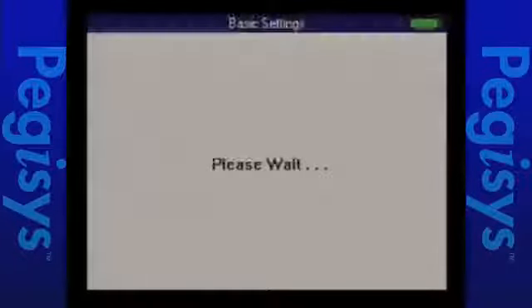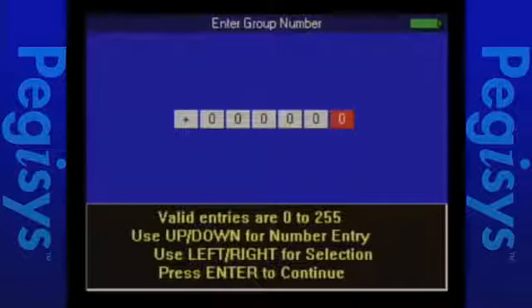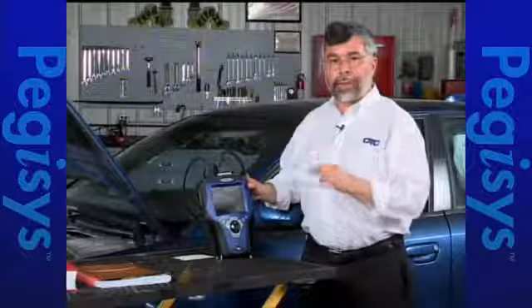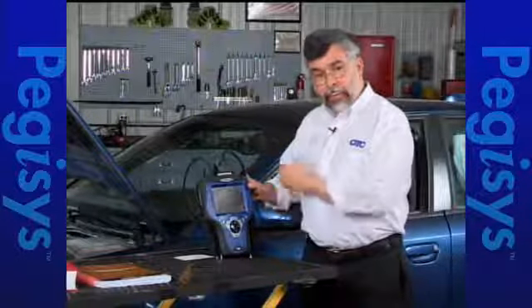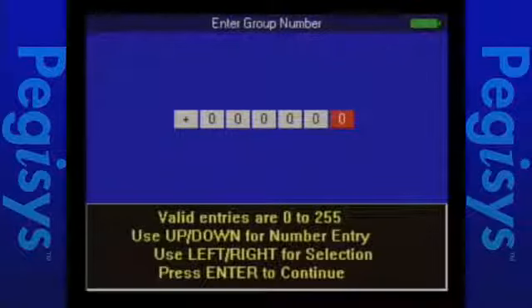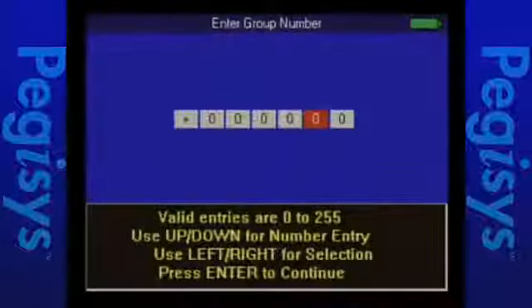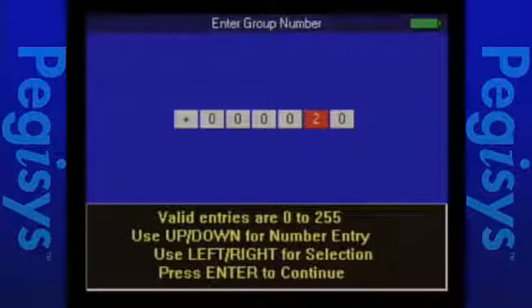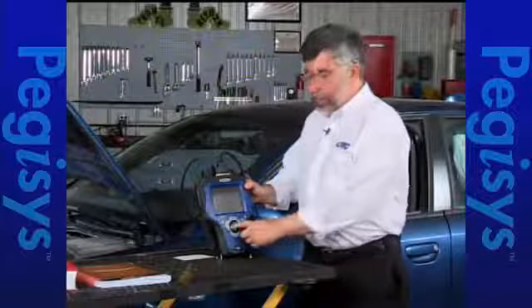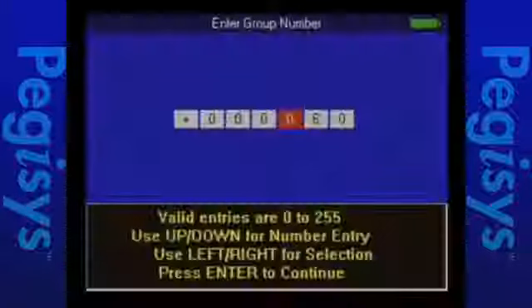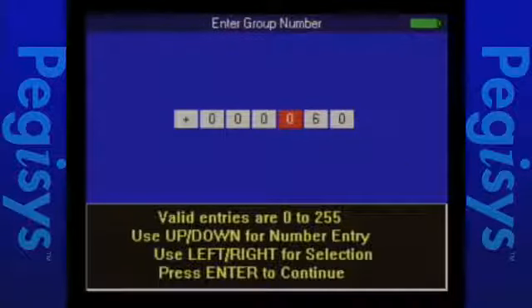When you do, up will come my group number block, and we're going to change our values. Remember, the number I'm looking for is 060. So I've got the furthest one to the right, the 0, highlighted in red. You would change that number if you had to by scrolling up or down. So I'm going to bring it back to 0. I'm going to scroll over to the next digit. You'll notice the second one's now highlighted in red, the second one from the right. I'm going to scroll up till I get to 6. If I had to change my 3rd digit, which I don't because it's already at 0, I would scroll to the left once more, highlighting my 3rd digit from the right, which is now 0, and I could change it up or down by scrolling up or down. So, oops, screwed up.